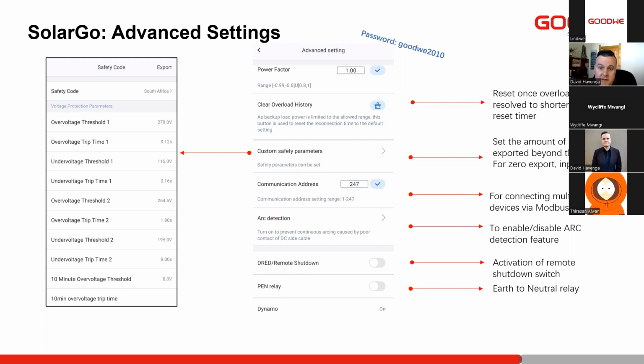Next, we have arc detection, as I mentioned, that optional extra that you can order. If we are seeing arc detection faults and we've not ordered it with the device, we can go in here and just make sure that the function has been disabled, or sometimes it might be enabled by default. Lastly, we have some other features like the remote shutdown or DRED connection for Australia. Yeah, we can disable that. We also have a PE to neutral relay. Depending on the country codes you select, this will be enabled automatically. 50 Hz default will not be able to work with the PEN relay. That's your earth to neutral relay.